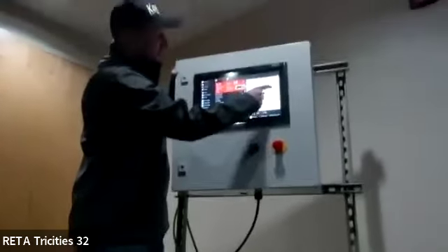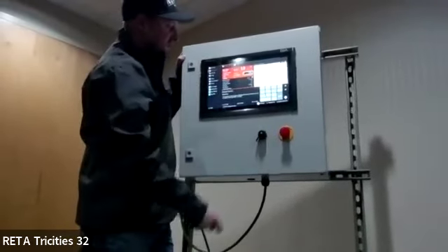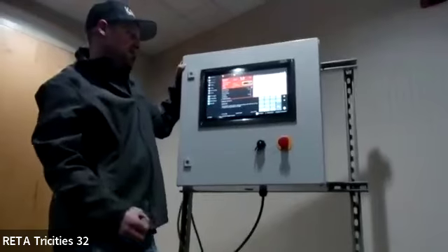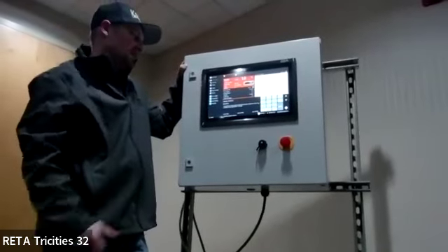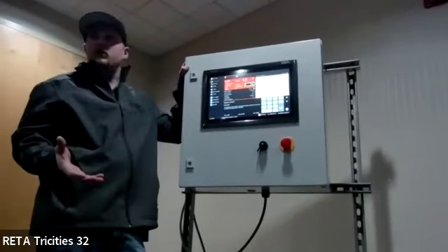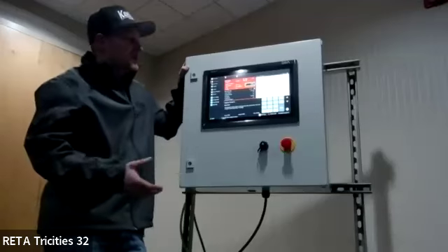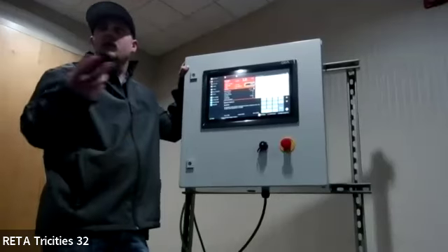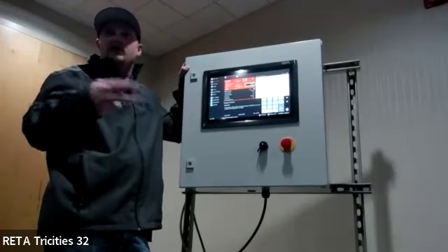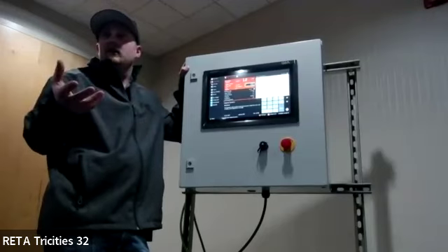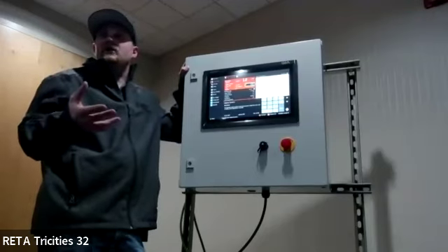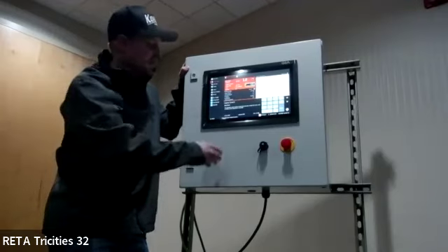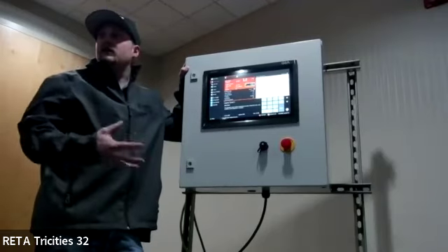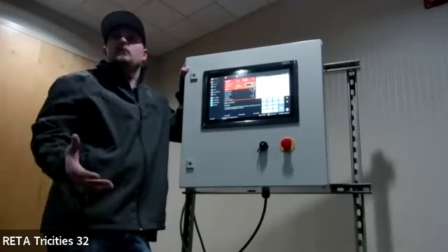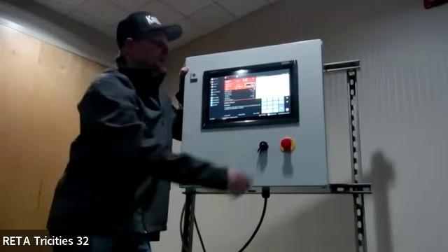So basically you would set that up as the set point right here. You have your dead bands and your proportional bands. Those are going to be the range above and below the set point within which there are no capacity control adjustments. So with a 2 pound dead band, you can be over 2 pounds or under 2 pounds, and it's not going to make any capacity changes. Those are actually adjustable within 0.1, so you can run it as tight as you want, up to 0.1 PSID.